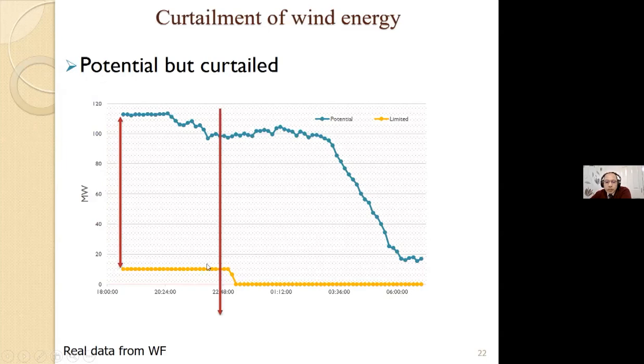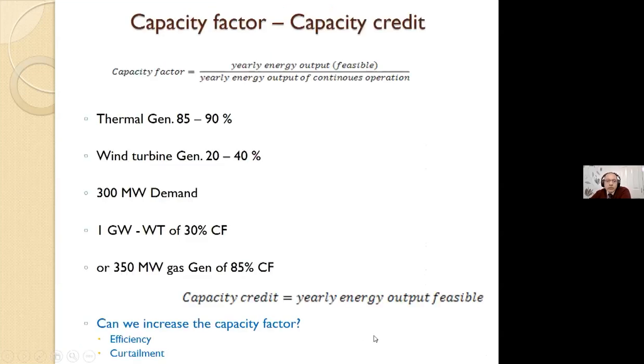So why don't we wait until it's really the low production time of potential? Why not wait until here, even here? Why don't we use even this 18, 19 megawatts of energy produced by the wind farm, instead of completely curtailing it to zero? It starts at 6 o'clock in the morning, so the load will start picking up toward the first morning peak in this case. So we have a problem: we produce energy, but we don't use it.